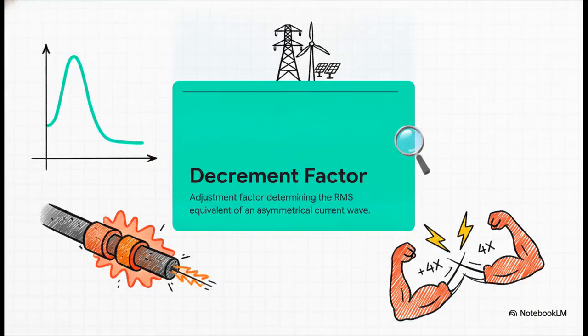But, physics is rarely perfectly neat. Fault currents aren't smooth alternating waves. They have an initial DC offset, which we calculate using a decrement factor. This offset essentially makes the current asymmetrical. So instead of a smooth, rhythmic push, the grid takes a sudden, violent shove. This pushes temperatures way higher, and incredibly, it exerts mechanical forces almost 4 times greater than a perfectly symmetrical current. The physical abuse the hardware has to endure is just immense.